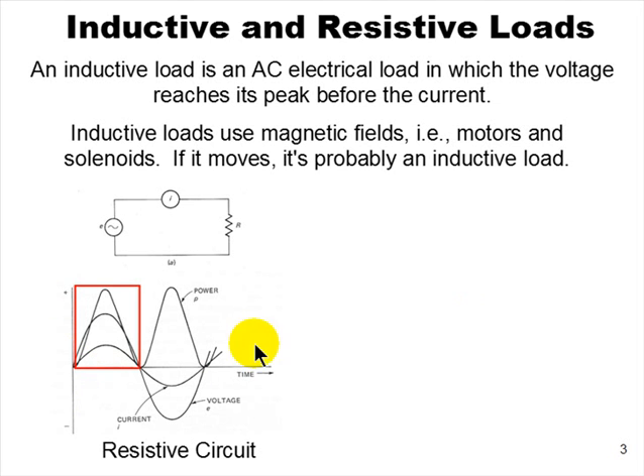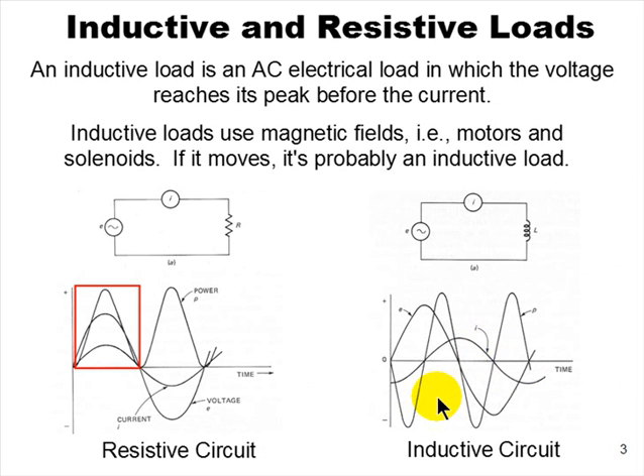This happens. Inductive load. Holy cow, looks like this. Take this one phase here. Here's inductive. Now here's your voltage, and we said it peaked before the amperage. Here's your amperage line. That's your amperage line. So the voltage peaks. This is time. Remember, this is 0 minutes, seconds, whatever, and this is positive seconds. So the voltage peaks, the amperage peaks over here, and the power, the VA, peaks at some point in between, because this is that multiplied by this.